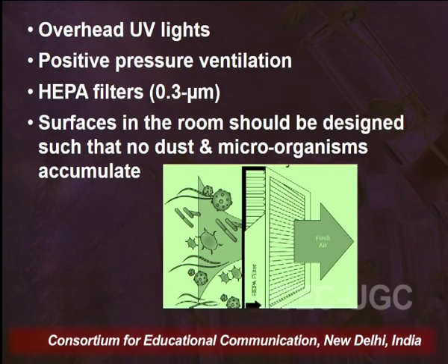Again, the surfaces used to prepare the transfer hoods should be designed in such a manner that no dust or microorganisms accumulate on the surface. Again, I will emphasize that porous surfaces should always be avoided while preparing the working benches in the media preparation room or in the transfer room. Preferably the working benches should have a surface without any joint, because these joints also act as a source of contamination. They also act as a source of dust and microorganism deposition.